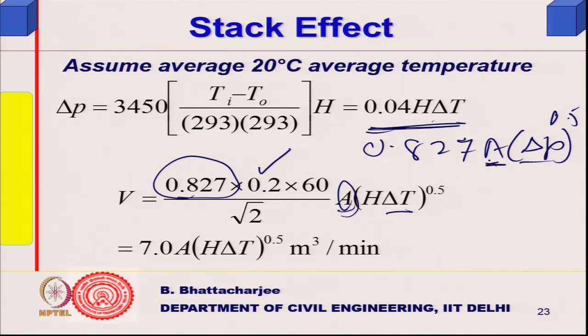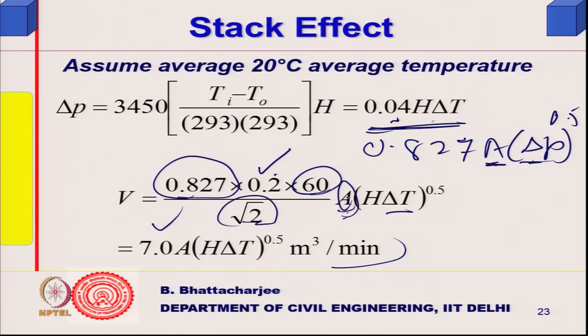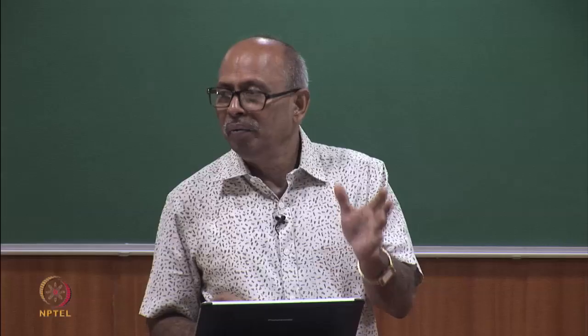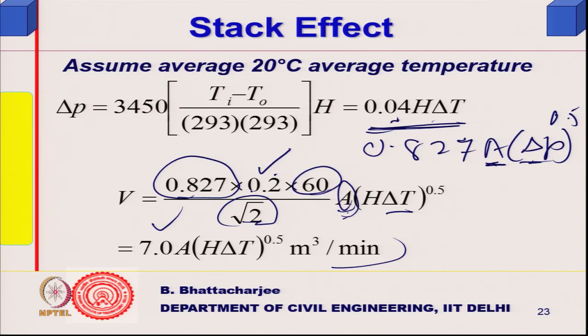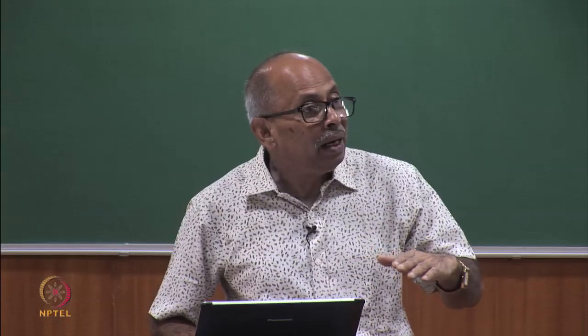Taking the equivalent area and multiplying by 60 to convert to m³/minute, the flow formula comes out to approximately 7.0 times A times the square root of (H times delta T) m³/min, where A is the equivalent area of inlet equals outlet, H is height between openings, and delta T is inside-outside temperature difference. This formula is found in SP 41.